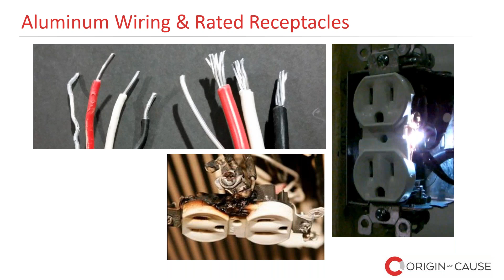So how do you deal with aluminum wiring? Well, a lot of the older cables that we used were rated for 60 degrees and 75 degrees and may not be suitable for modern fixtures. The Electrical Safety Authority, ESA, has come up with some solutions, one of them being asking the installers to take further action when replacing, for example, light fixtures, such as using 90 degrees Celsius heat shrink, and that would give some more insulation against failure.